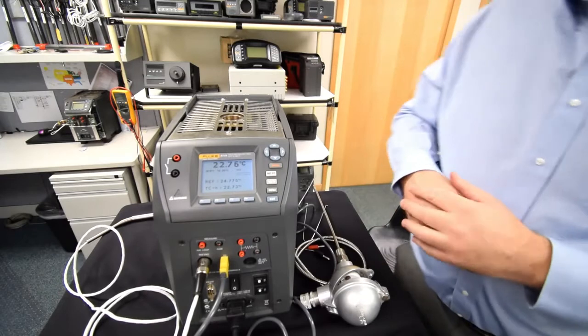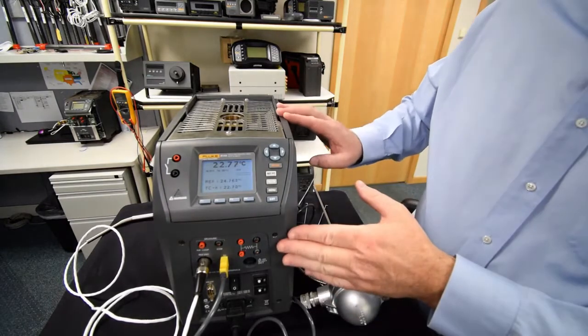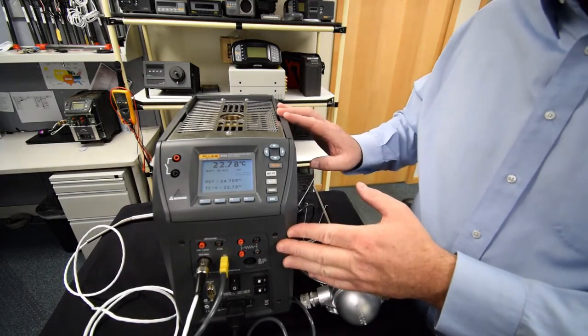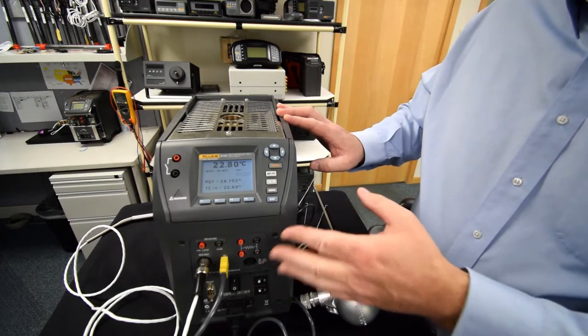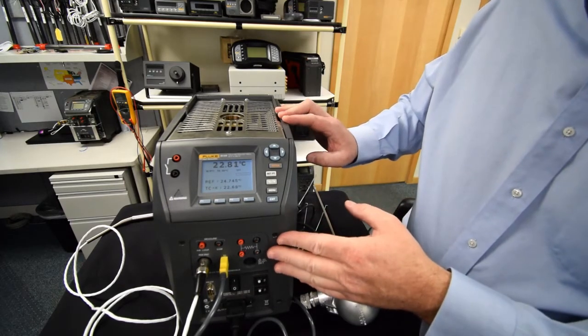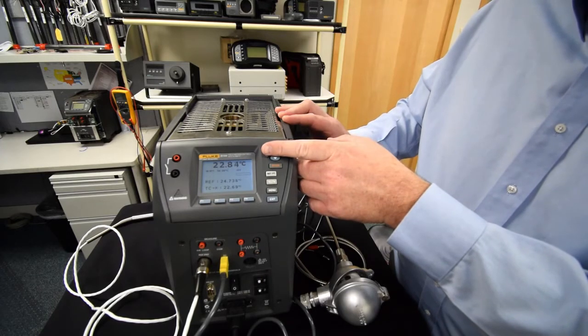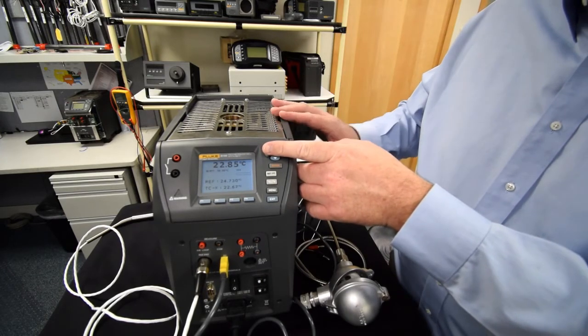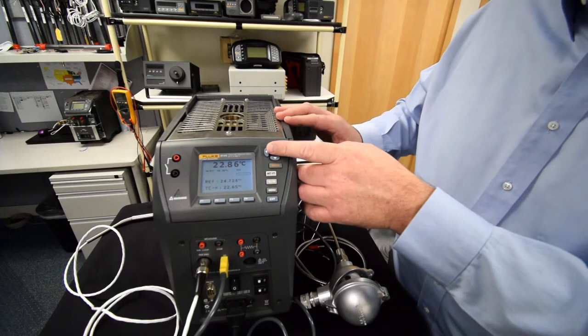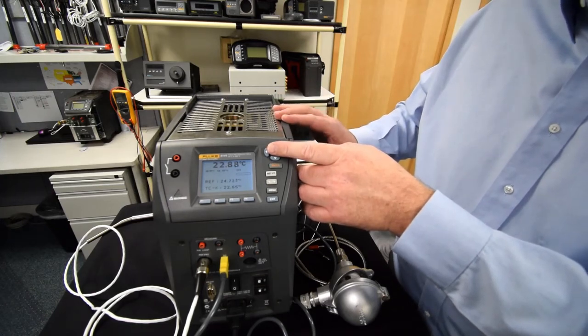The unit itself that we have here is outfitted with our process options. So the units can be purchased with or without these. I'm showcasing this.